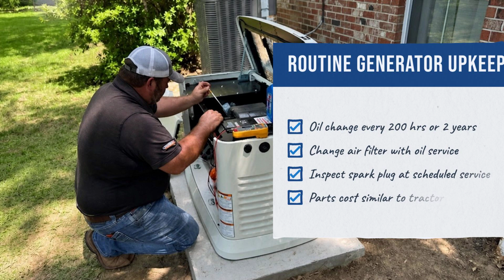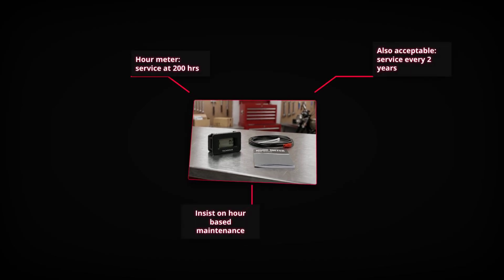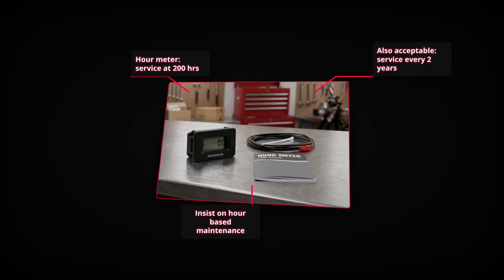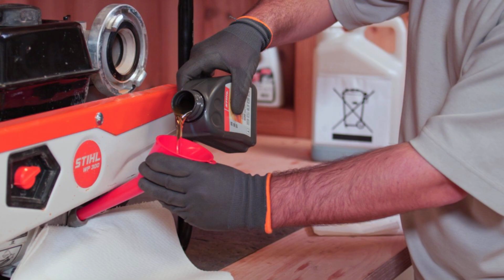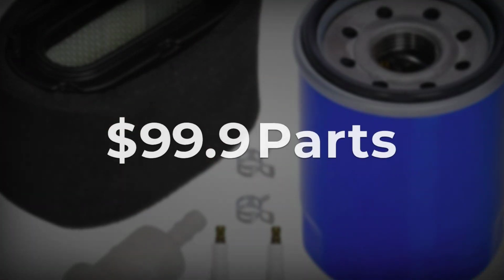A basic air-cooled standby generator needs an oil change, a filter change, and a spark plug check on a schedule tied to running hours, commonly every 200 hours or every 2 years, not automatically every single year no matter what. The parts for that visit, a filter, plugs, a small synthetic oil kit, run under $100 total.